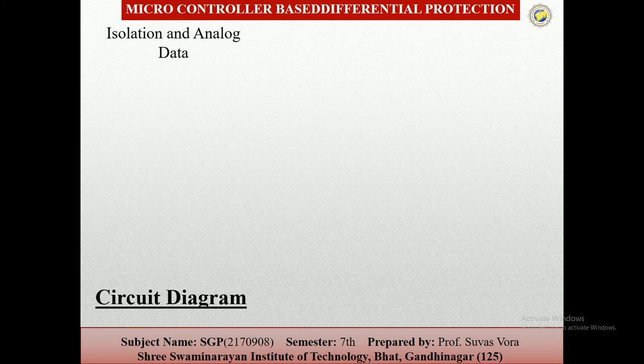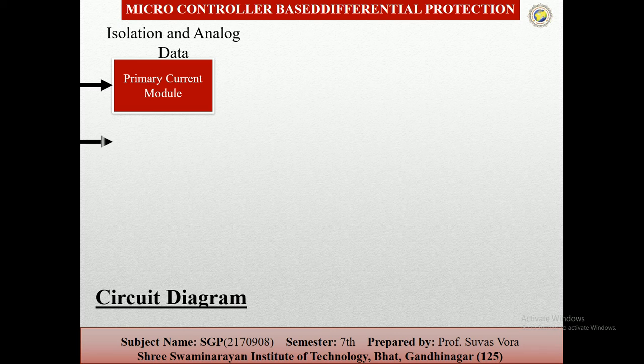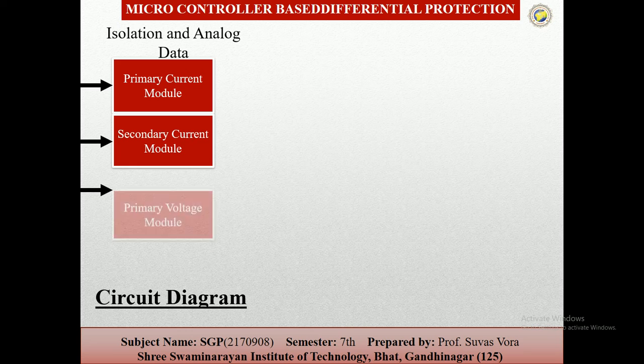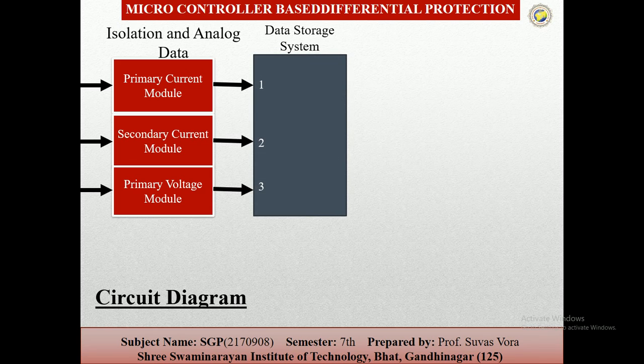So the microcontroller is a compact integrated circuit designed to govern specific operations in embedded systems, यानी कि embedded controller use करते हैं. A typical microcontroller includes the processor, memory and input-output peripheral devices on a single chip. So here the first one is isolating the analog data coming from the system. The first one is the primary side current module, then the secondary side current module, and then also the primary voltage module. अगर we know that if the current is faulty current, at that time the voltage is also different. So these are measured and go to the data storage system.